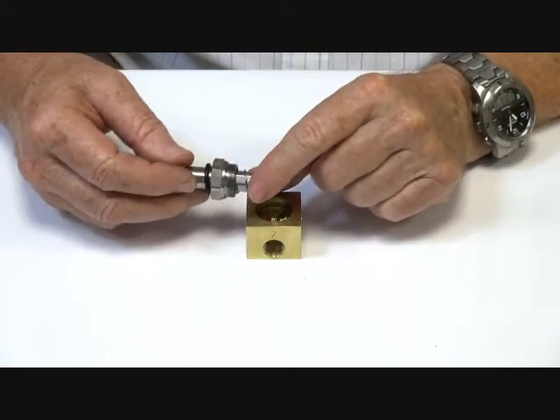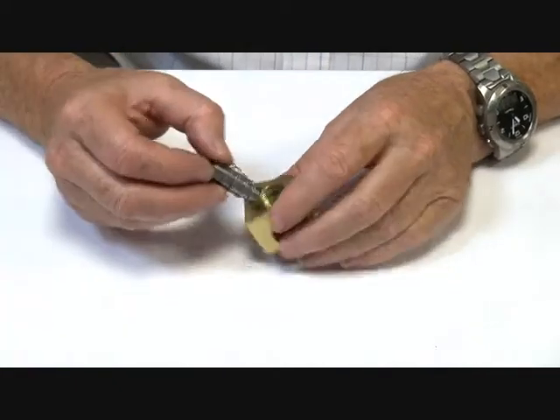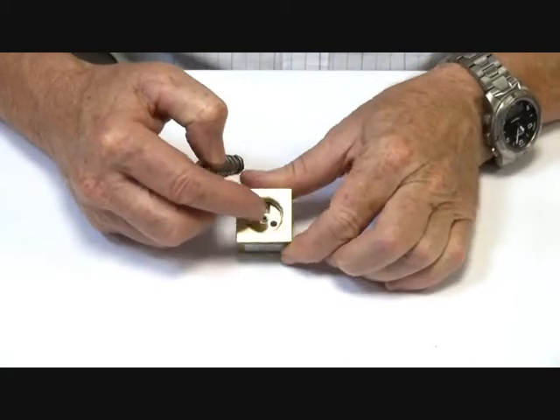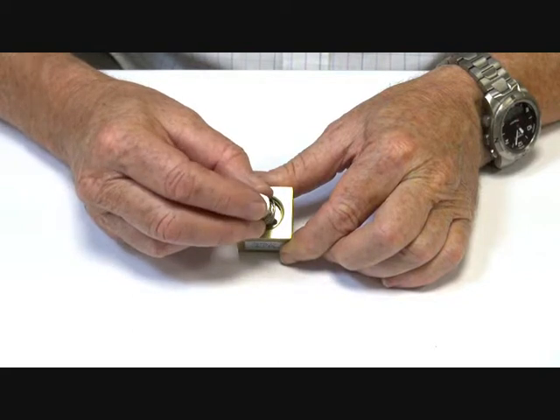We have the armature assembly here. The armature is normally sitting down on the seat and the media is coming in through the side entry here, sitting on top of the armature and assisted close with the spring.